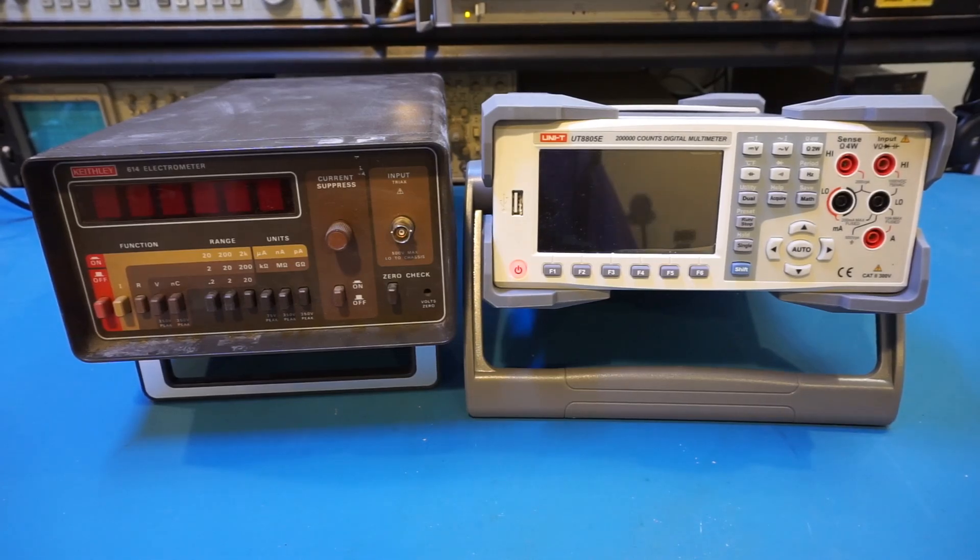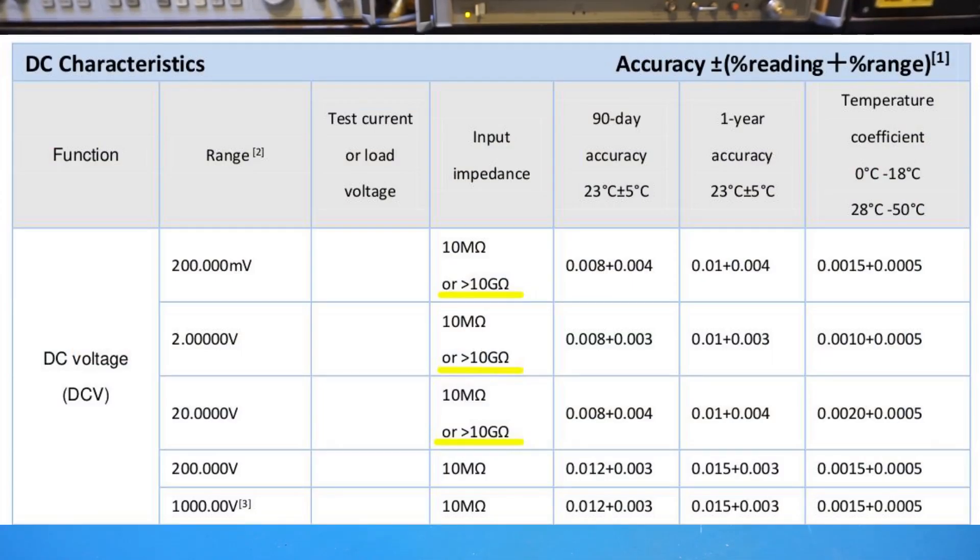Now, one specification that is very impressive is its input impedance in voltage ranges under 20 volts. According to the spec sheet, the input impedance is greater than 10 gigaohms in the 200 millivolts, 2 volts, and the 20 volts ranges.